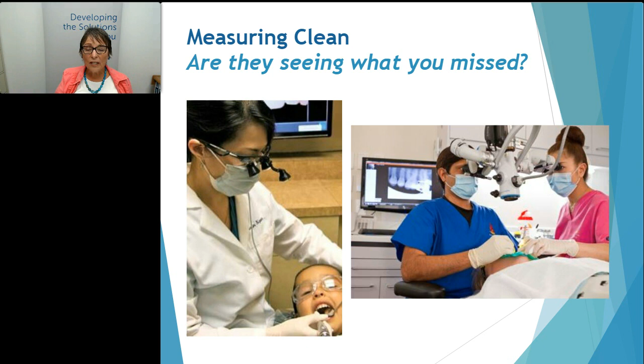Now we're going to get into measuring both our devices and our cleaning results. Magnification has definitely made it more apparent when our instruments aren't clean. Patient safety is paramount, but it's also embarrassing when someone responsible for processing instruments sees something on them in the middle of a procedure with magnification. There are many reasons why we need to check what we're doing and check the results of our cleaning process. There are two basic things we're trying to figure out: whether our devices are working correctly, and whether we have residual soil.